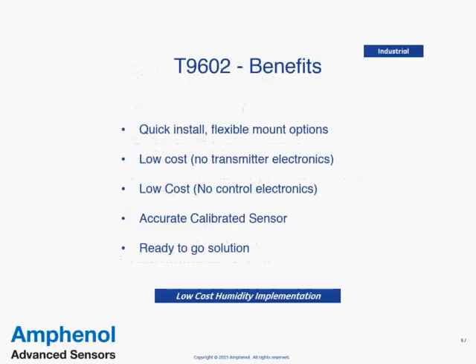Looking at a few benefits: it's very quick to install, very flexible with mounting options, and by taking out the transmitter and control electronics we saw earlier, we've substantially reduced the cost. It's an already calibrated sensor, so it's a ready-to-go solution for either installer or customer. Typically the sensor works out at something like half the cost of a typical temperature and humidity transmitter.